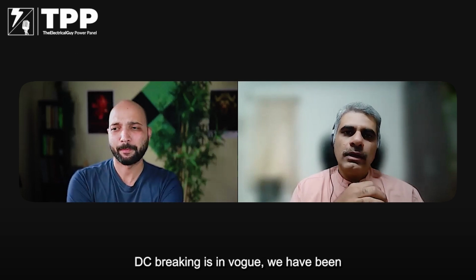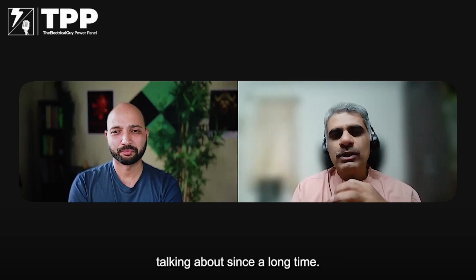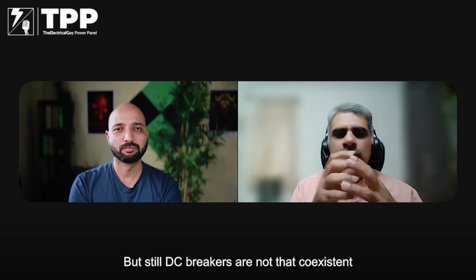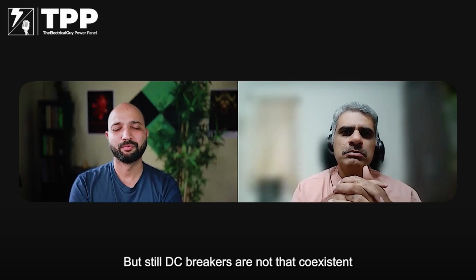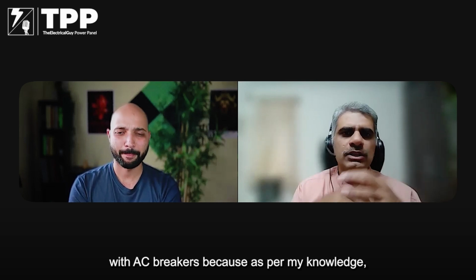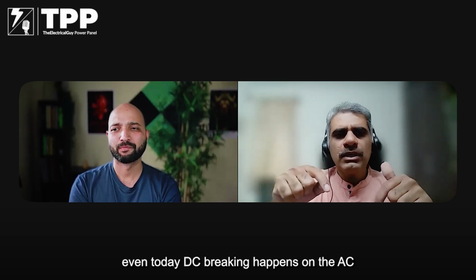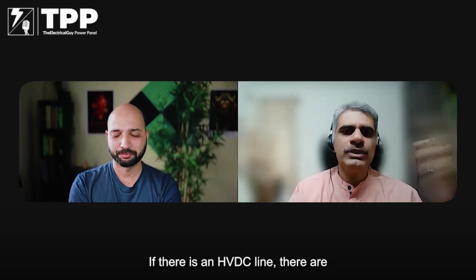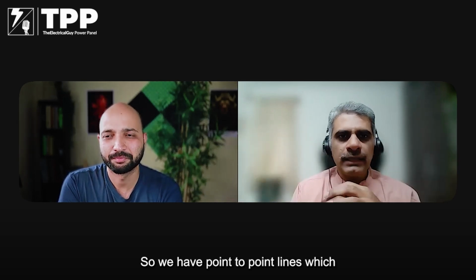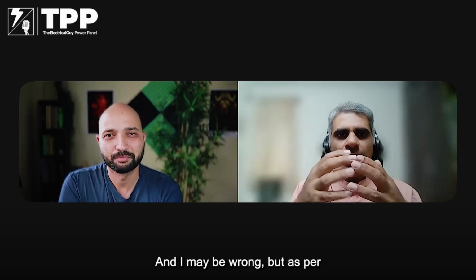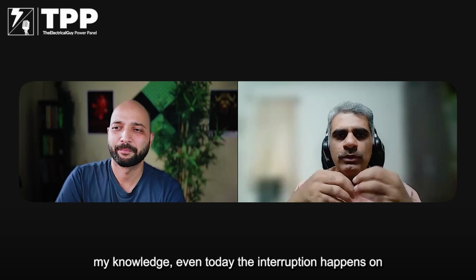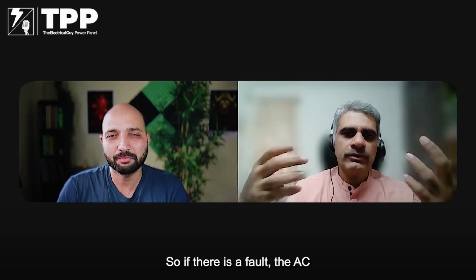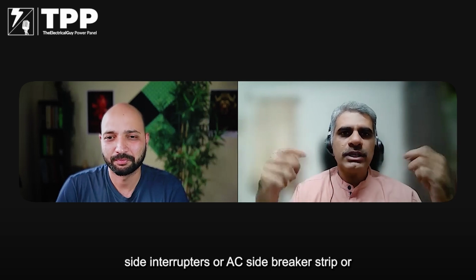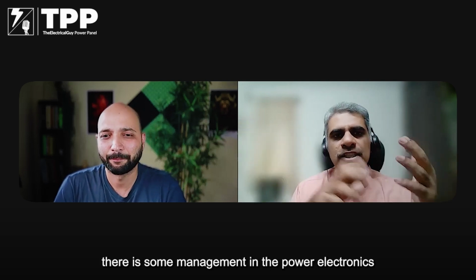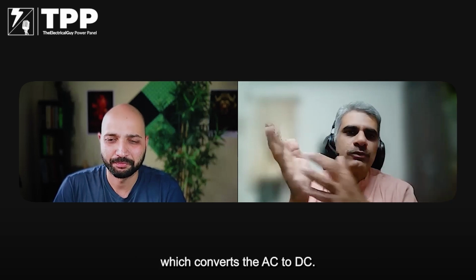DC breaking is in vogue. We have been talking about it for a long time, but still DC breakers are not that coexistent with AC breakers, because, as per my knowledge, even today DC breaking happens on the AC side. If there is an HVDC line, there are converter stations. We have point-to-point lines which are called HVDC links. And I may be wrong, but as per my knowledge, even today the interruption happens on the AC side. So if there's a fault, the AC side interrupters or AC side breakers trip, or there is some management in the power electronics which converts the AC to DC.